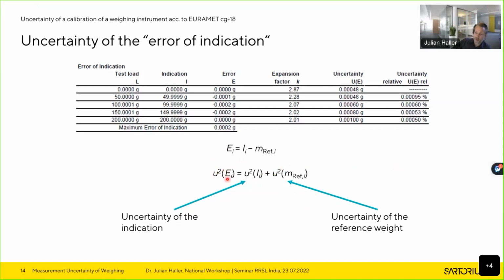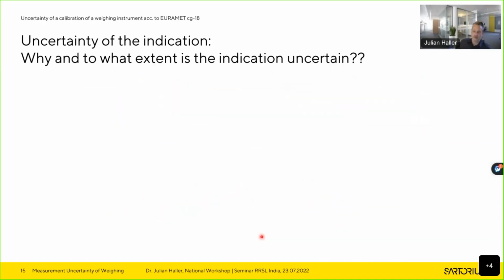But the general characteristics of this formula, that you have to consider the uncertainty of the indication and the uncertainty of the reference weight, that is straightforward. Now let's have a look at these two contributions. First one, the uncertainty of the indication. You might ask, why and to what extent is the indication uncertain? You read the indication 99.99 grams. What is the uncertainty connected to that?